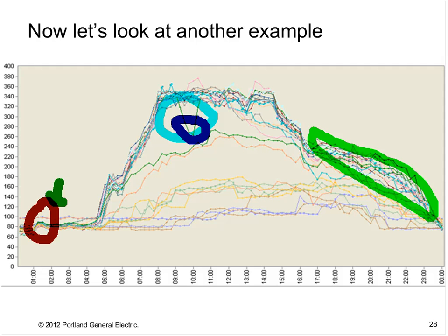This is actually a school district office where you'll see these two lines at 100 kW that are usually between 60 and 80. Basically, that was from the computers turning on at night and running their antivirus software and checks. The only problem is they could turn the computers on, but the software wouldn't let them turn them off. So they spotted that and got different computer software that let them shut the computers off after they were done running virus checks. So very good.